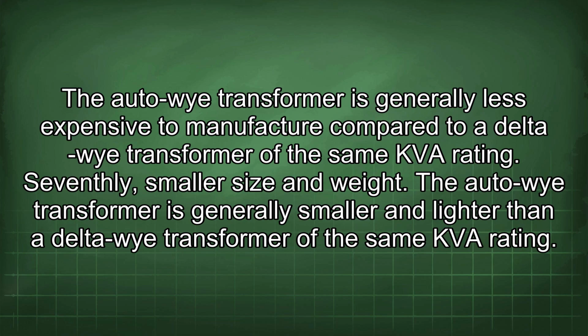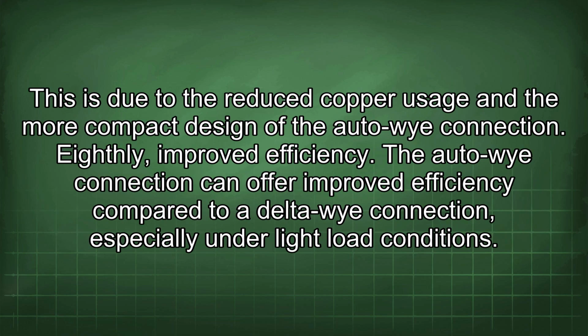Seventhly, smaller size and weight. The Auto-Wye transformer is generally smaller and lighter than a delta-Y transformer of the same kVA rating. This is due to the reduced copper usage and the more compact design of the Auto-Wye connection.